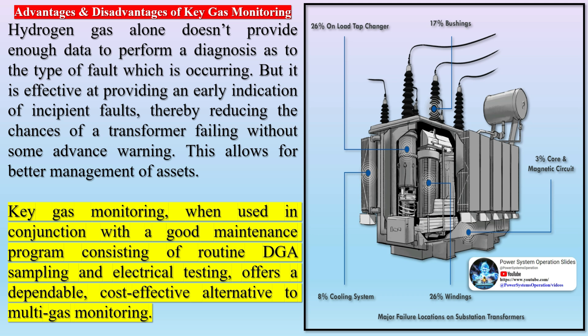Advantages and disadvantages of key gas monitoring: hydrogen gas alone doesn't provide enough data to perform a diagnosis as to the type of fault which is occurring. But it is effective at providing an early indication of incipient faults, thereby reducing the chances of a transformer failing without some advance warning, which allows for better management of assets. Key gas monitoring, when used in conjunction with a good maintenance program consisting of routine DGA sampling and electrical testing, offers a dependable, cost-effective alternative to multi-gas monitoring.